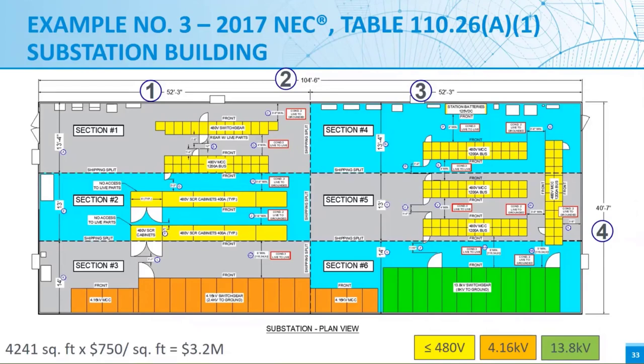This one that we're looking at right here is designed in accordance with the 2017 NEC and the minimum spacing requirements prior to this change. The main items that I want to point out in this slide are the equipment that is involved in this substation, along with the overall dimensions that are going to be shown by bubbles 1 through 4. As you can see by the different colors that are gray and blue, we're going to have 6 modules or building sections with the maximum dimension based on the maximum allowable shipping size over most roadways in the United States. Each of these sections are approximately 14 feet by 55 foot, and the shipping splits are indicated by the dashed lines.